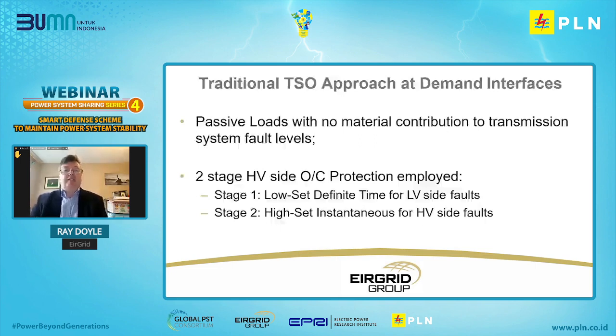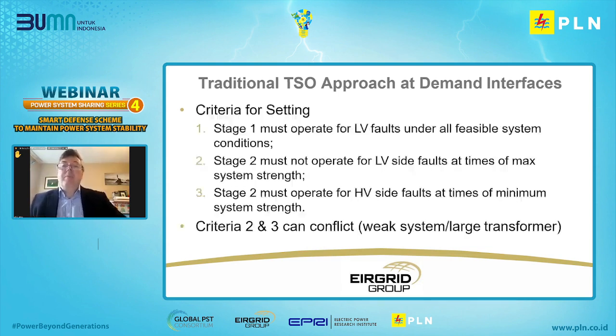Our traditional TSO approach at demand interfaces, with passive load and no material contribution to transmission system faults, was to typically deploy two-stage HV side overcurrent protection: stage one with a low set definite time for clearing LV side faults, and stage two, high set instantaneous for HV side faults. So next slide, please. Our criteria for setting these are: stage one must operate for LV faults under all feasible network conditions. Stage two must not operate for LV faults at times of maximum short circuit strength. Stage two must operate for HV side faults at times of minimum system strength. Again, because of the changing nature of the system, criteria 2 and 3 can conflict when we've got a weak power system and large transformers. Okay, so next slide, please.